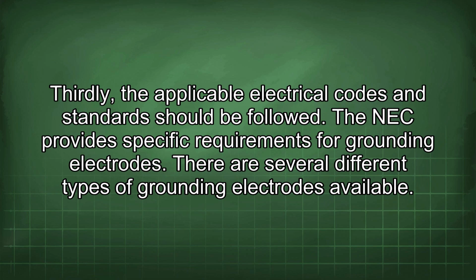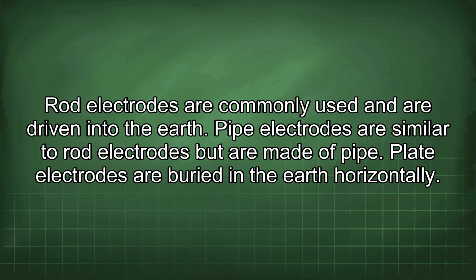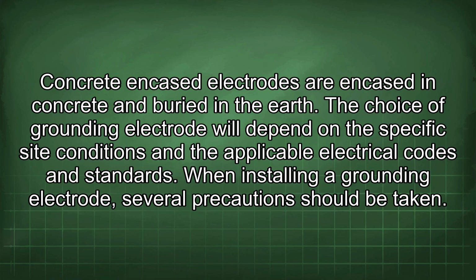There are several different types of grounding electrodes available. Rod electrodes are commonly used and are driven into the earth. Pipe electrodes are similar to rod electrodes but are made of pipe. Plate electrodes are buried in the earth horizontally. Concrete encased electrodes are encased in concrete and buried in the earth. The choice of grounding electrode will depend on the specific site conditions and the applicable electrical codes and standards.